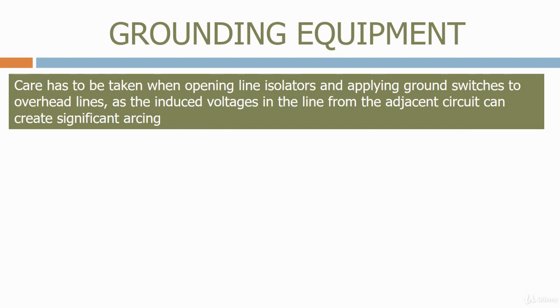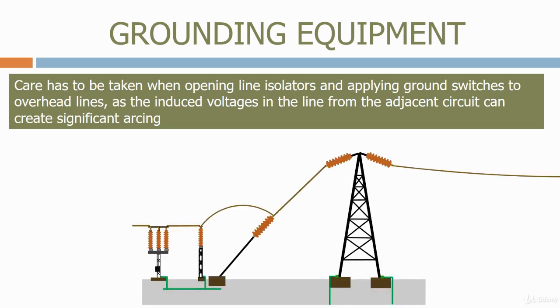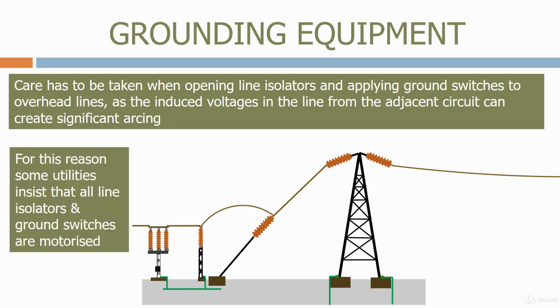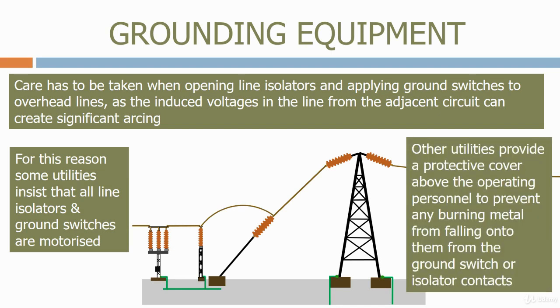Care has to be taken when opening line isolators and applying ground switches to overhead lines, as the induced voltages in the line from the adjacent circuit can create significant arcing. Here's a typical overhead line coming down to an air-insulated substation. For this reason, some utilities insist that all line isolators and ground switches are motorized. Other utilities provide a protective cover above the operating personnel to prevent any burning metal from falling onto them from the ground switch or isolator contacts.